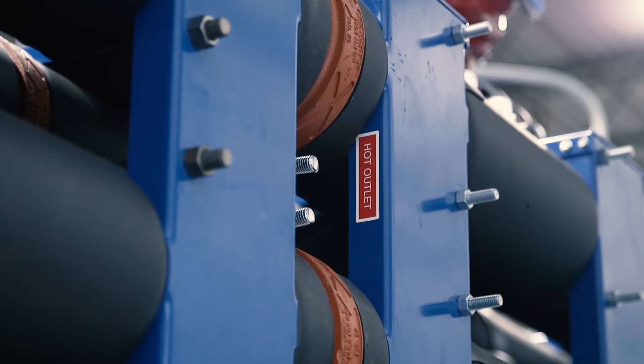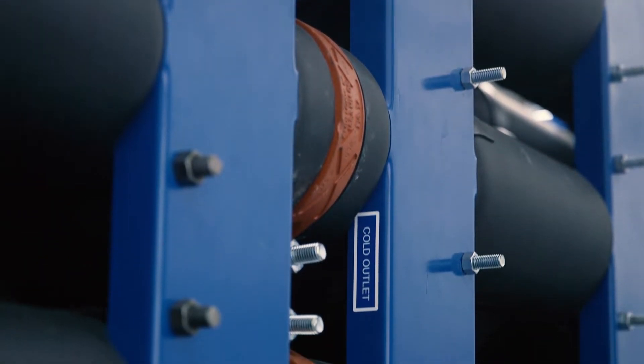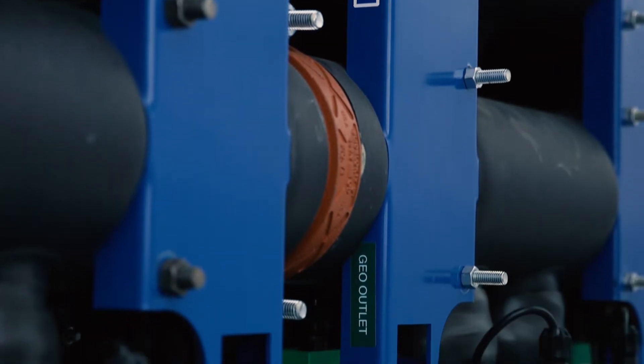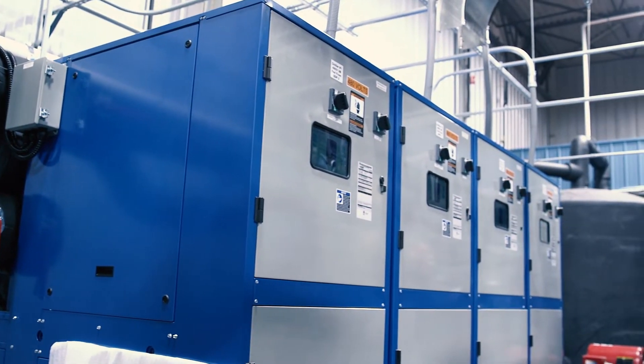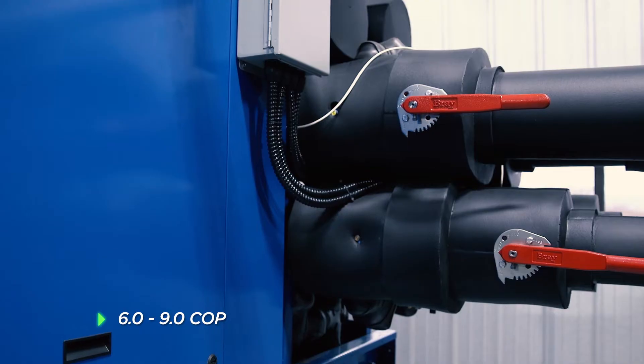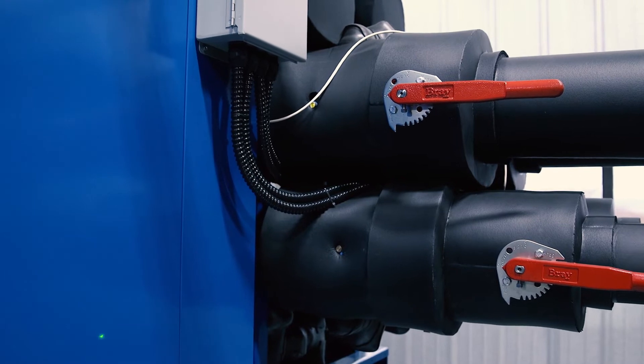The six-pipe rack allows complete conditioning flexibility. The upper piping connects to the hot tank, the middle piping connects to the chilled tank, and the lower piping is connected to the geosource. When possible, chillers are placed between the two tanks to condition both to desired dual set points, all at efficiencies of 6 to 9 COP. The geosource is connected once one of the set points has been reached.